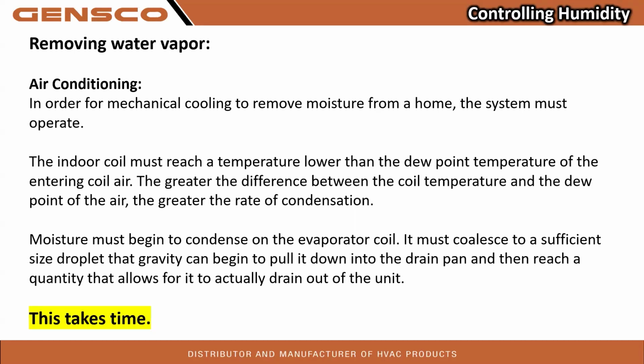condensation. Now, this is one place where mini splits in the Mitsubishi world aren't that great. Their target coil temps are not 40 degrees like the universal standard in air conditioning, how it's been since I got into this industry. It's more like 50 degrees. We're not going to do as much condensating on the coil because we don't have a huge difference between coil temp and the dew point. If we had a 40-degree coil, and sometimes we do, there are instances where we are much colder than that, but that's not what we're targeting.